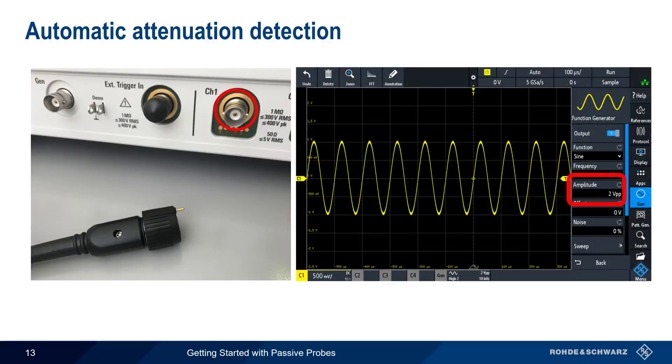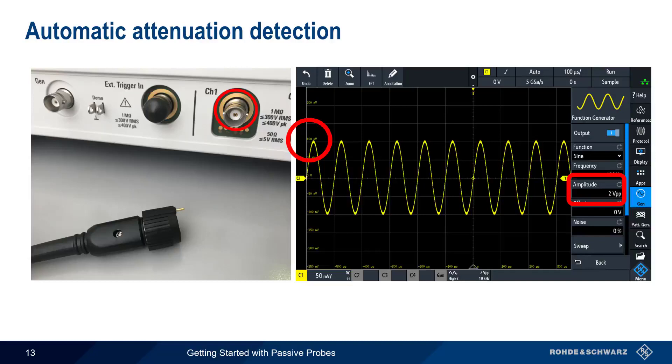One final topic we touched on earlier is automatic attenuation detection. Recall that 10x passive probes reduce, or attenuate, the signal level by a factor of 10. As mentioned earlier, a small pin on the scope end of the probe is sensed by a ring around the scope input, and this tells the scope that the measured signal level has been reduced by a factor of 10. For example, if we generate a 2 volt peak-to-peak sine wave and measure it with a 10x probe, we'll see a peak voltage of 1 volt if the 10x probe is properly detected, but only 100 millivolts if the probe attenuation is not automatically detected. It's especially important to be aware of this if you're using 10x probes from a different manufacturer, or if you're using probes that can be switched between 1x and 10x.